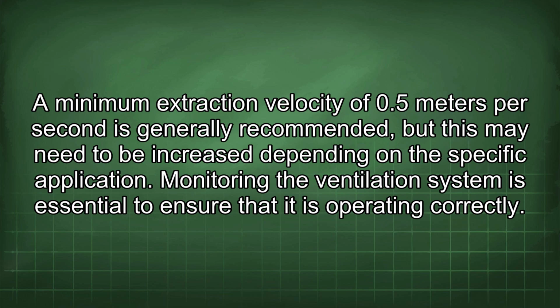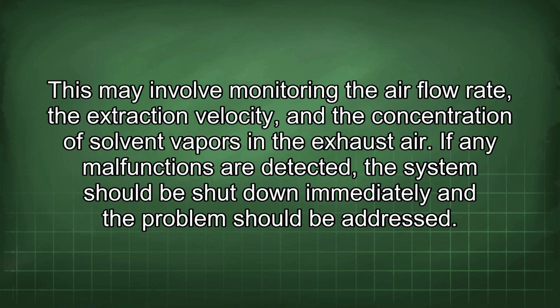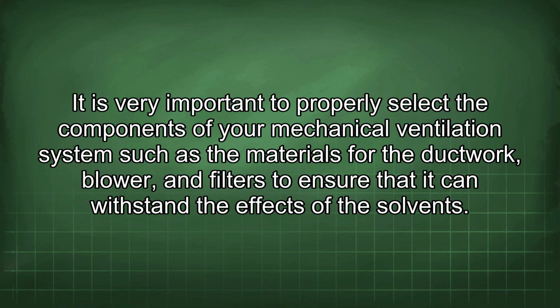Monitoring the ventilation system is essential to ensure that it is operating correctly. This may involve monitoring the airflow rate, the extraction velocity, and the concentration of solvent vapors in the exhaust air. If any malfunctions are detected, the system should be shut down immediately and the problem should be addressed. It is very important to properly select the components of your mechanical ventilation system, such as the materials for the ductwork, blower, and filters, to ensure that it can withstand the effects of the solvents.